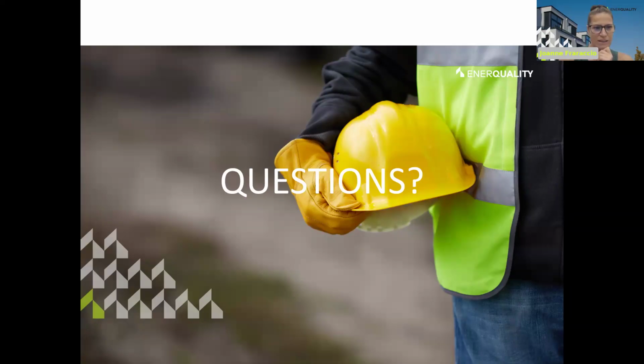Okay. And the last question from Ben was, is the drain water heat recovery tech usable for non-basement houses, or houses that are hooked up to a septic system that exits the house fairly high up the foundation wall? Yeah, so with septic, it's kind of the same as with slab on grade, depending on how low the exit is and how much vertical space you have, because you can install units on very short, like 20 inches, if you want to. But obviously, if you don't have enough headroom there, then we're looking at a two-story building where we would service the upstairs bathroom as our main target.